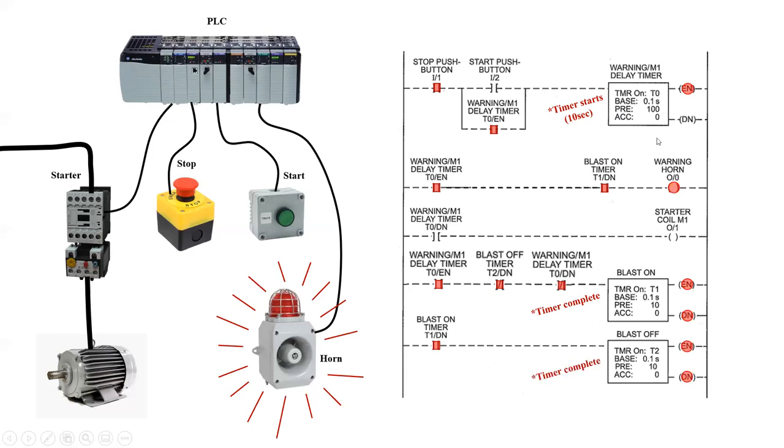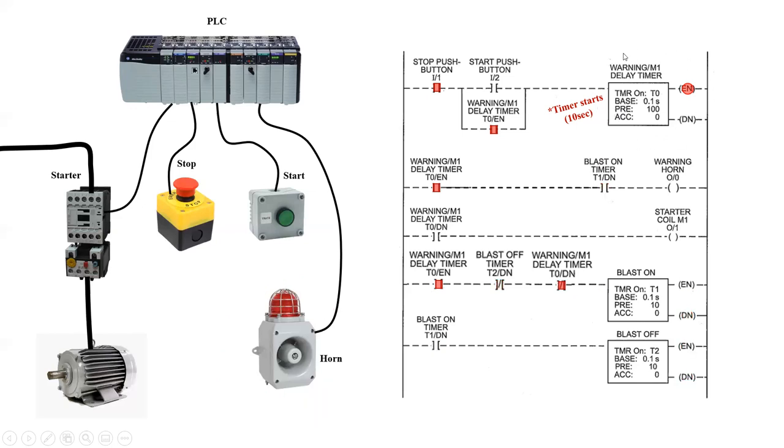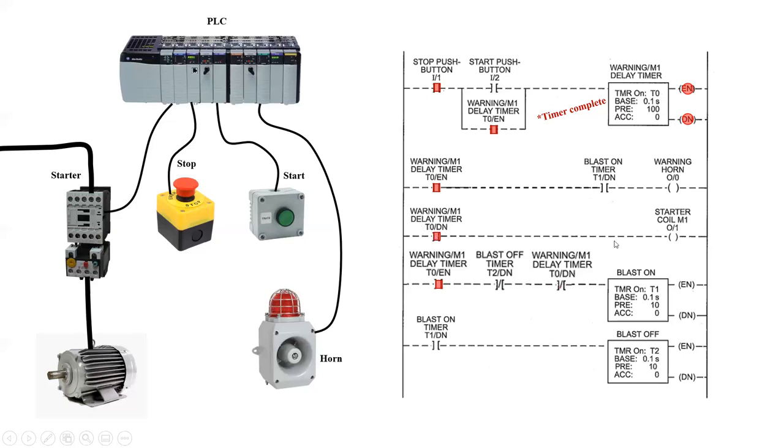After 10 seconds, this timer up here will time out. And when that occurs, the done coil on this timer will go on. And that will cause this internal bit to go false, and this internal bit to go true, thereby starting the motor coil.